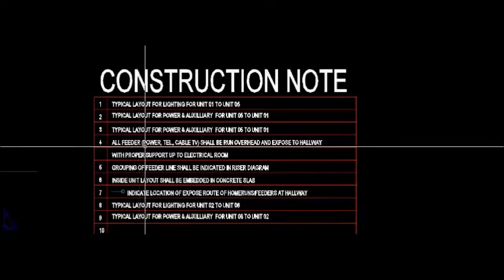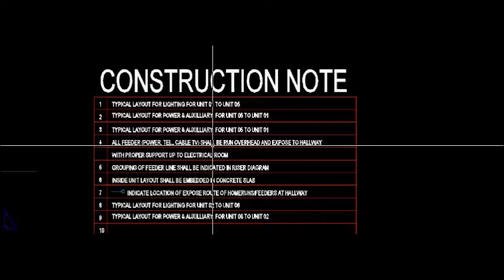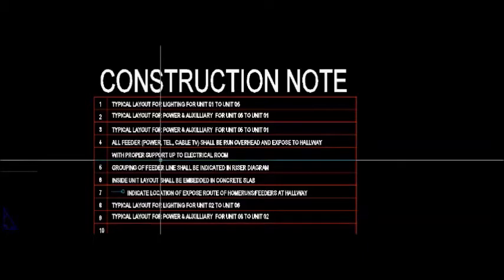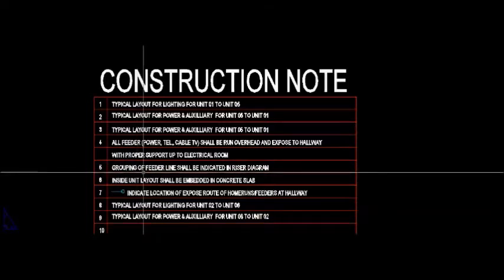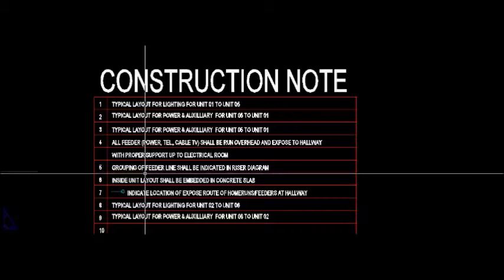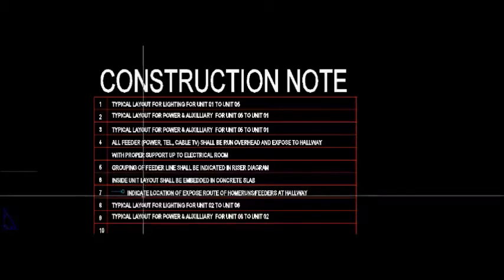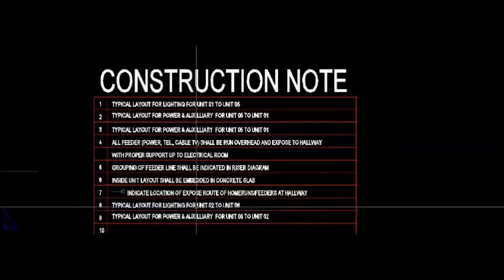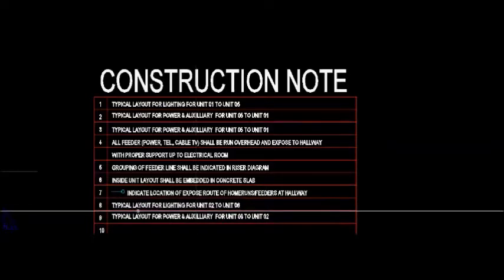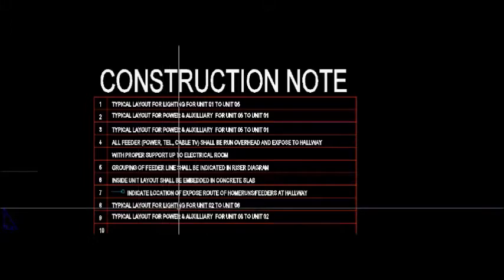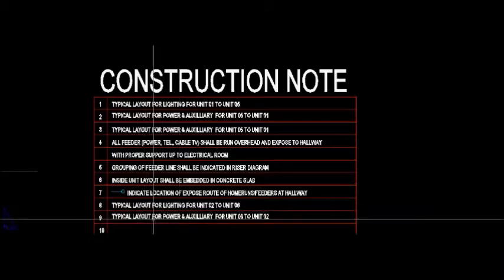All feeder, power, telephone, cable TV shall be run overhead and exposed to hallway with proper support up to electrical room. Grouping of feeder line shall be indicated in riser diagram. Inside unit layout shall be embedded in concrete slab. Indicate location of exposed route of home runs or feeders at hallway. Typical layout for lighting for Unit 2 to Unit 6. Typical layout for power and auxiliary for Unit 6 to Unit 2.